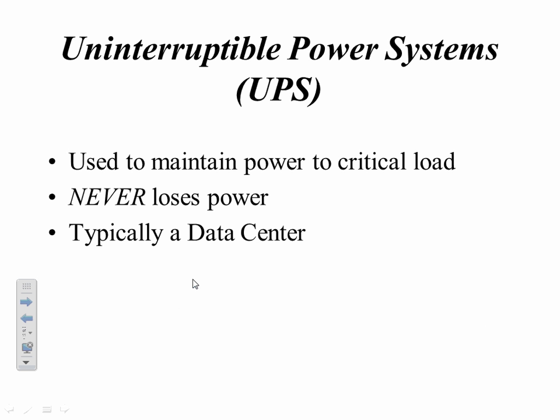All right, first one that I'm going to talk about is an uninterruptible power system, or UPS, very common today. And this is used to maintain power to a critical load, typically in IT, information technology centers. The guy that's running the computer operation for a company. And they are never to lose power. And this is typically done in a data center that's backing up extremely critical loads for factories, for financial operations, those kinds of things.